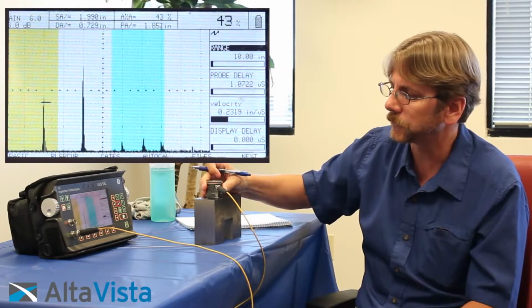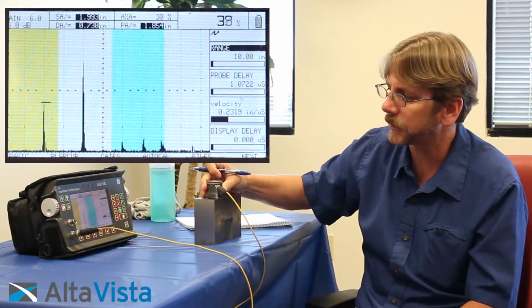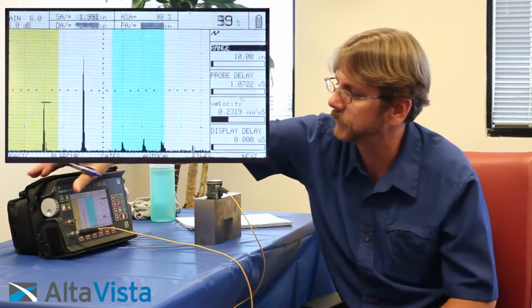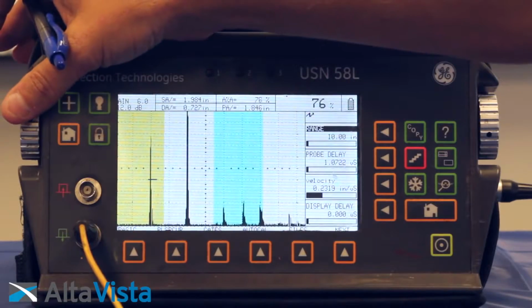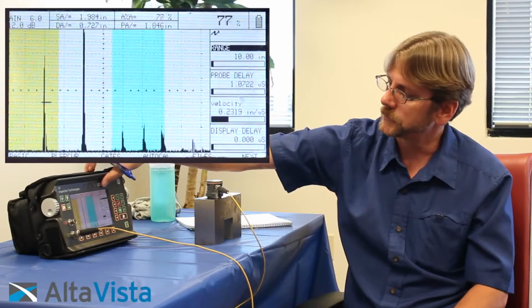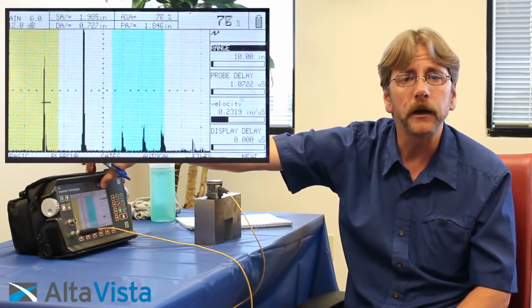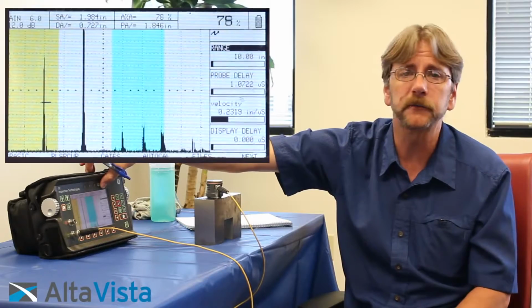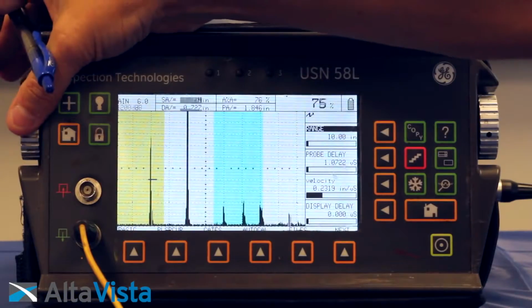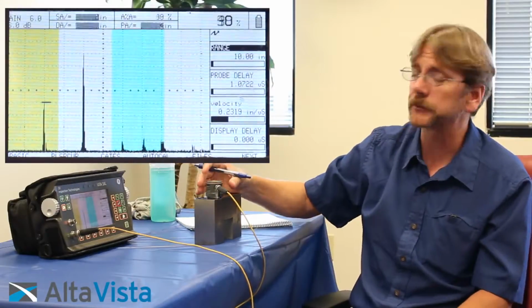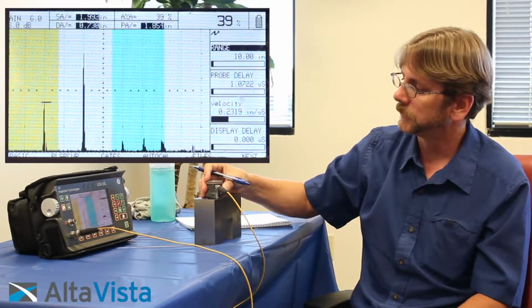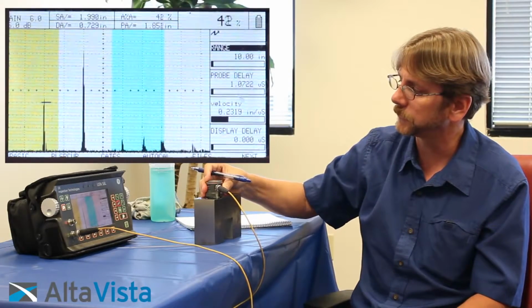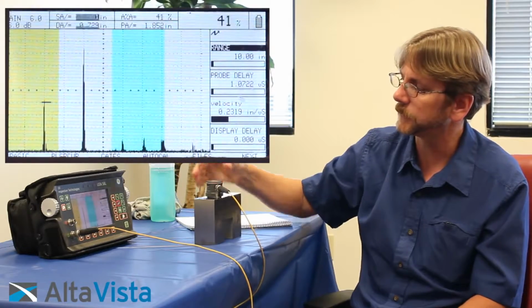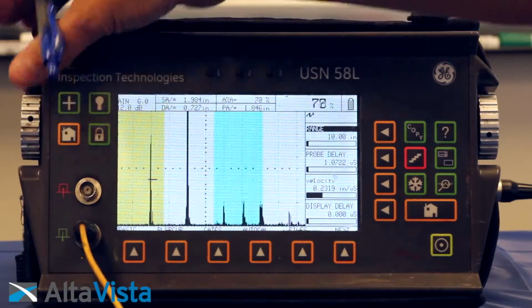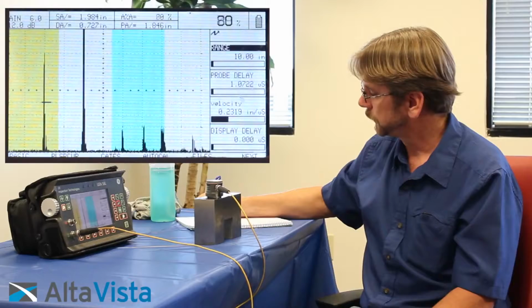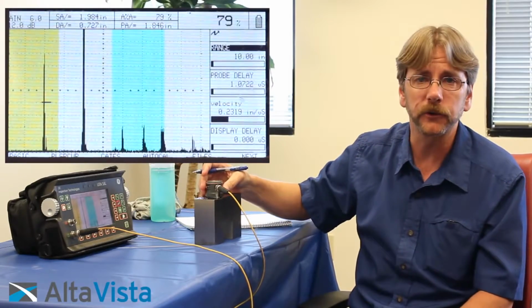So again, we're going to slide it towards the long portion of the block, lowering the indication strength, and increase by 6 dB. In this case, I'm a little bit low on my indication, so I'm going to back up that step and just verify that that's the correct number. So in this case, I'm at 39% full screen height instead of 40. So I'm going to go back until I get 40% full screen height. Right about there. Then I'm going to do it again. And I'm at 79. So it's just a way to verify that you have the correct values.